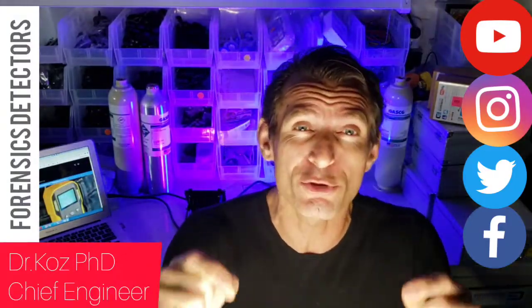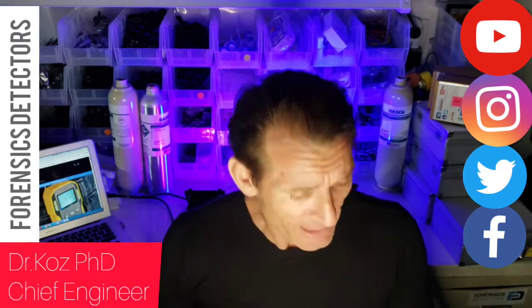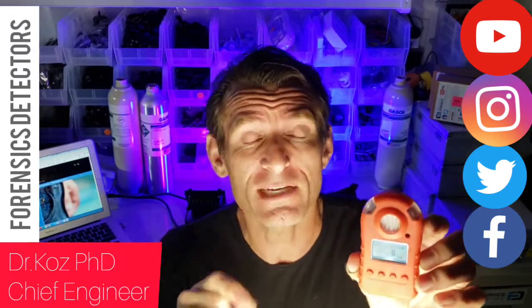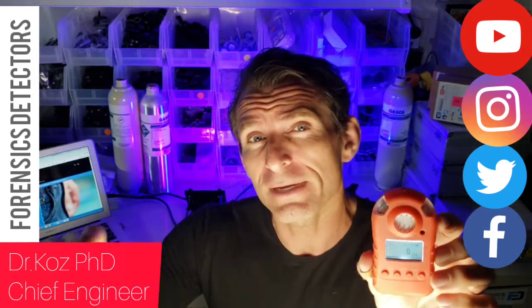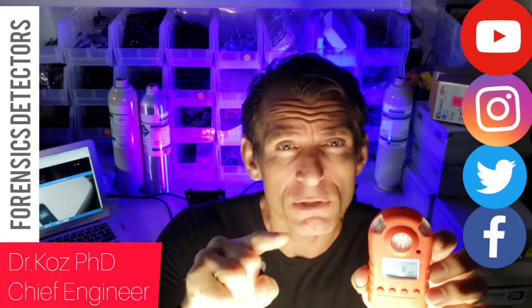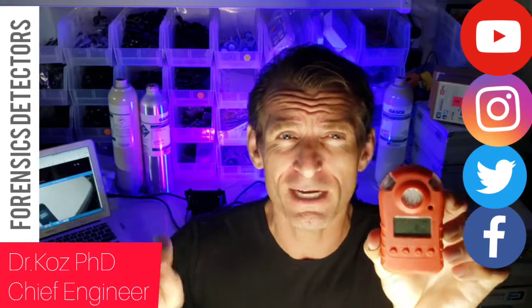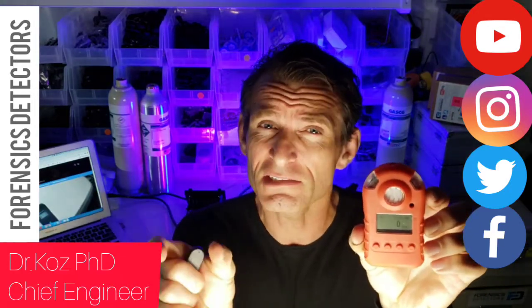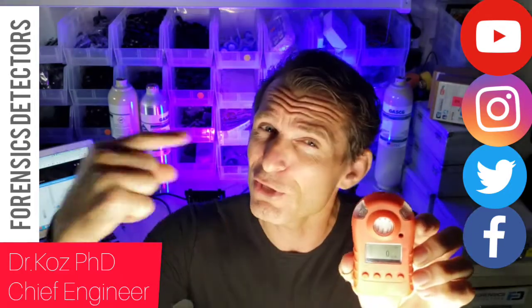I am your ozone analyzer detector expert. Today, we are presenting to you our newest member of our family. It's our high range ozone meter. High range, 0 to 100 parts per million. The standard detectors detect 0 to 20. This goes beyond that.